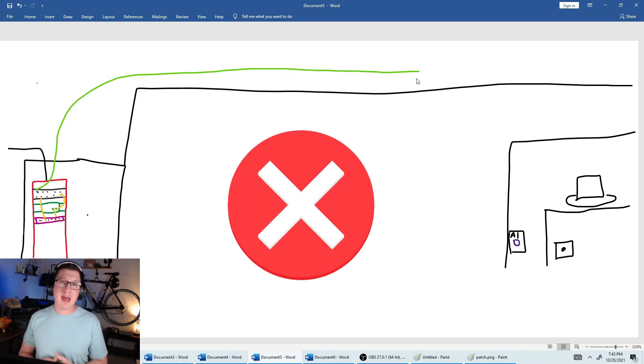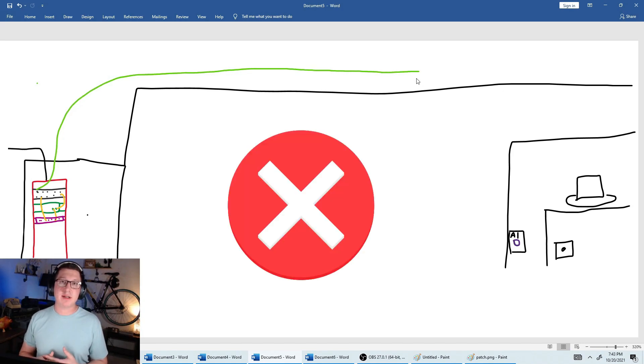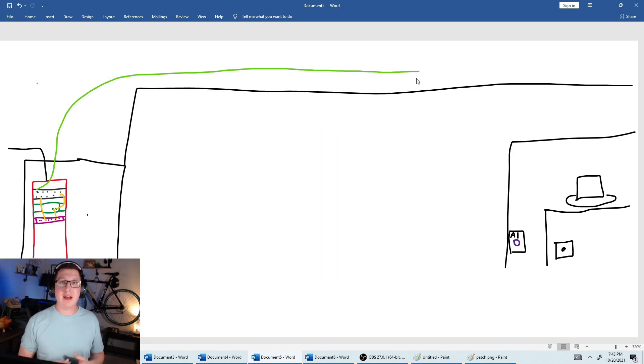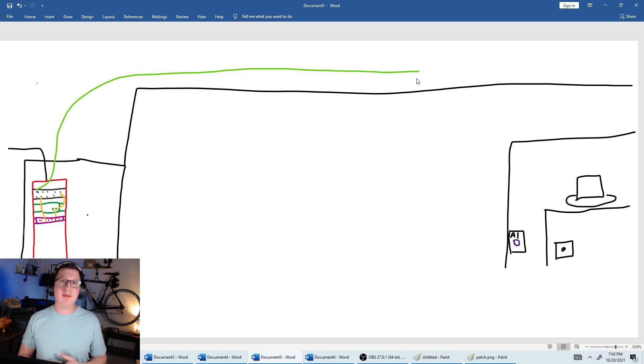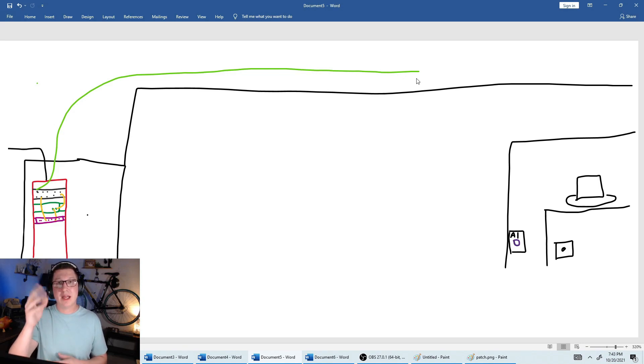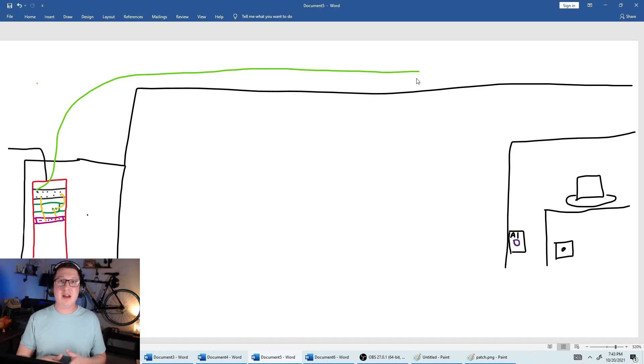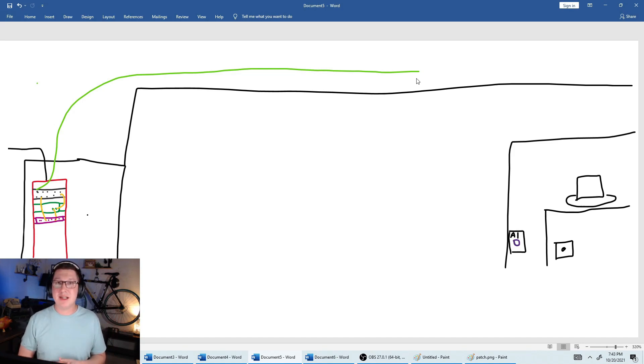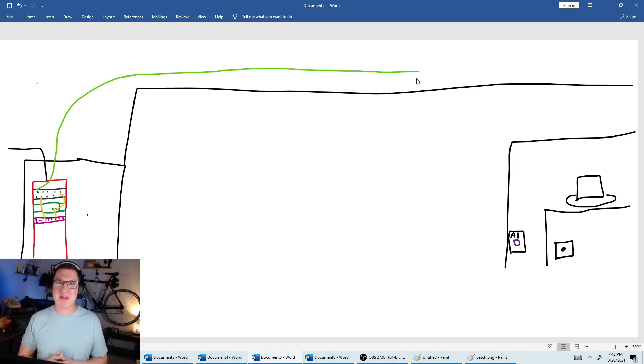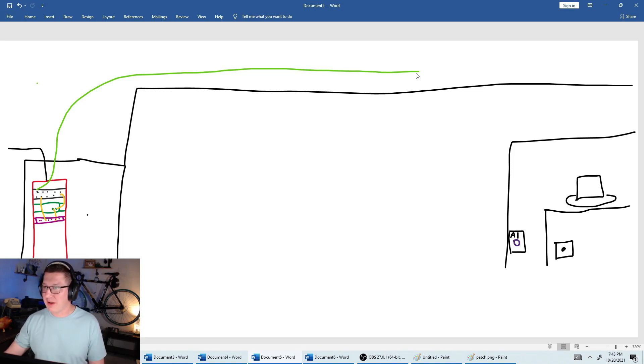When you guys start running cable, there is rules to running cable, especially when you're in a ceiling. You have to have plenum cable in a plenum ceiling. So that means if your HVAC is exhausting through the ceiling, and it's just going into the ceiling, and it's not going through another pipe, you have to have plenum cable, which means that when it burns, it doesn't get off any toxic fumes. So before you just start ripping cable through somewhere, realize that there's rules to it.